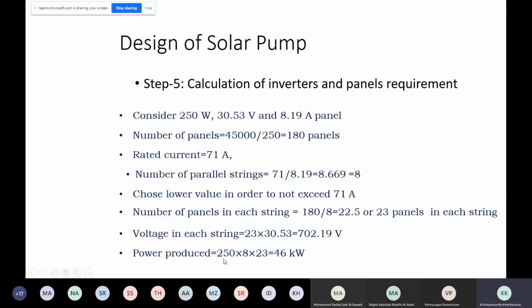I told you, we will not stop exactly at 45,000. You see here, 250 into 8 will be 2000. 2000 into 23 will be how much? 46,000. 46 kilowatt we have designed the panel. We will always design some little extra, because if any one fails, no issue. 46 kilowatt.